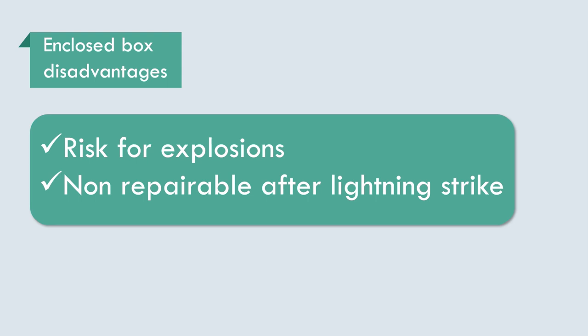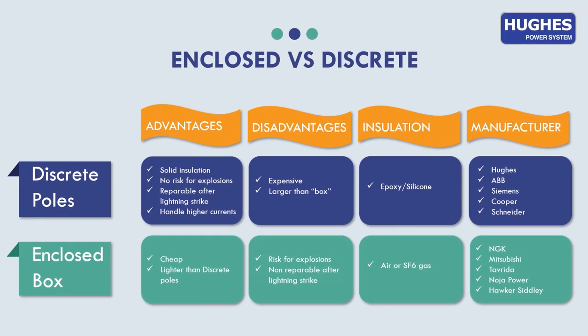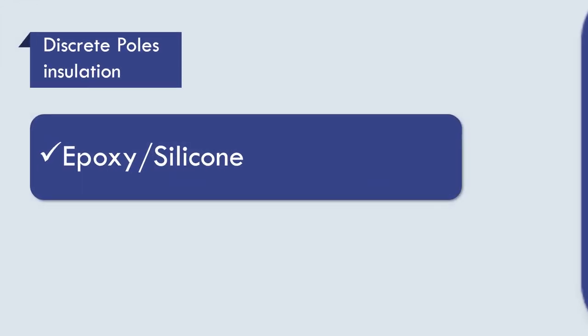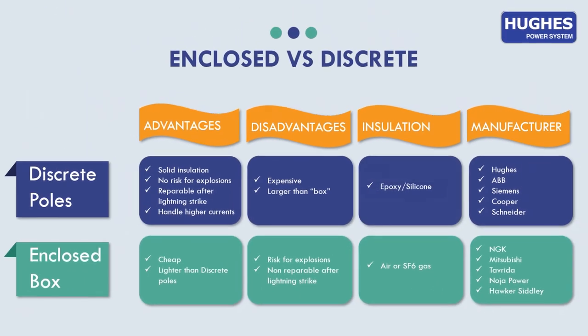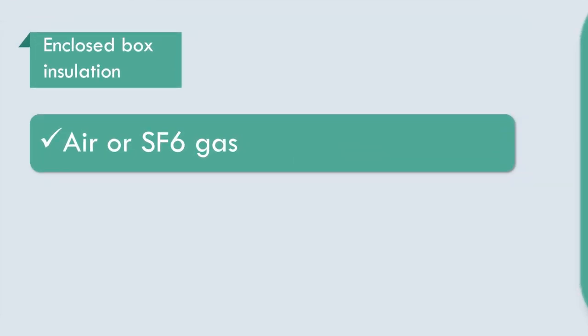Third parameter is insulation. For discrete poles, it is epoxy or silicone, which gives excellent protection against UV radiation or installation faults. For enclosed box, it is air or SF6 gas, which has a risk of gas leakage and is harmful for the environment.